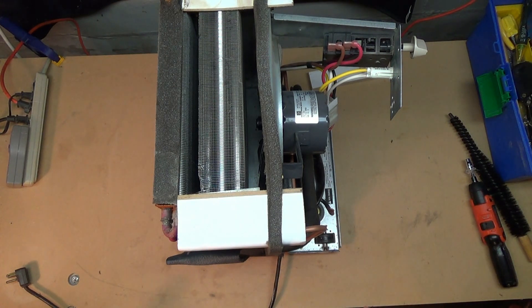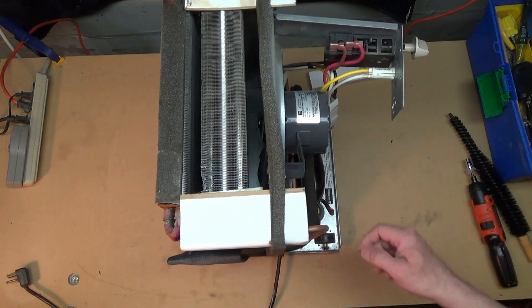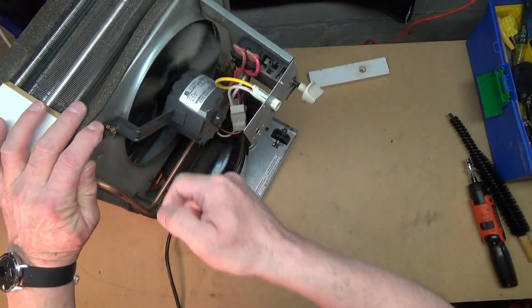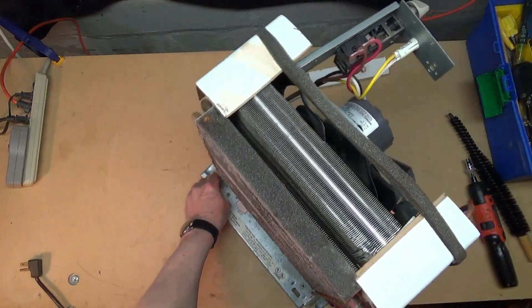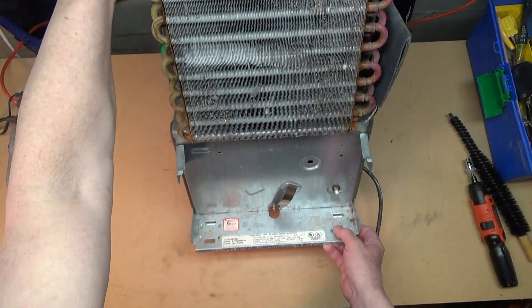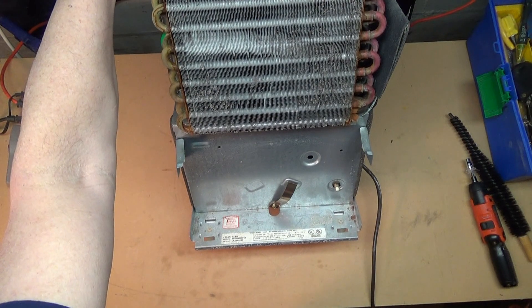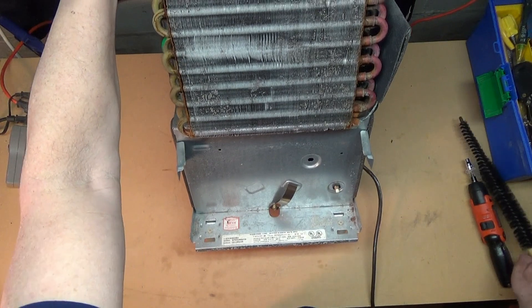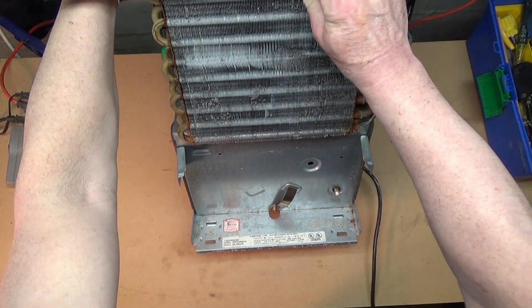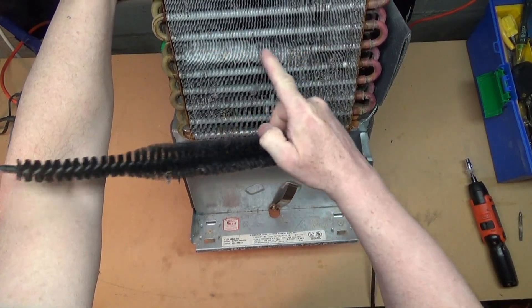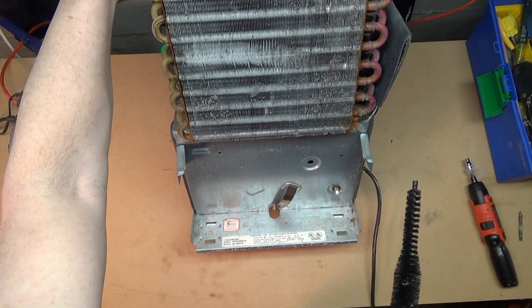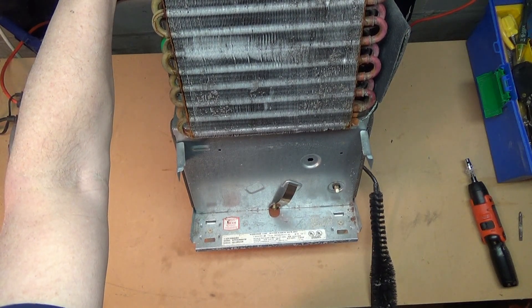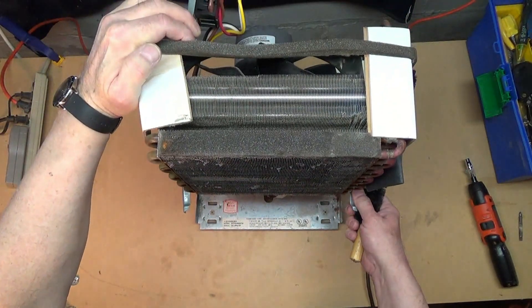When these ice up, things we look for are: number one, does the fan spin freely? And this fan does. The second thing we look for are plugged coils, because if they're plugged, then air won't flow across them and be reheated and flow back out. As you can see from looking at the front of this, they're pretty dirty and it looks like they've been smashed right across the front, and certainly no air is going to pass through there.